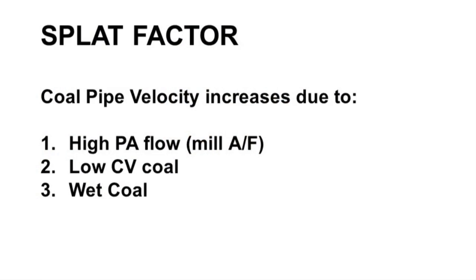I also wanted to suggest that I have seen wet coal cause wall slag problems in the past, and I had a tough time explaining why water or how wet the coal was an influence on the slagging behavior. But I now know that wet coal has the same impact on the pulverizers as low calorific value coal. In other words, wet coal takes a higher coal flow rate and potentially more primary airflow to try to dry the wetness. And so wet coal actually influences the pulverizer performance and could potentially influence the splat factor and resulting wall slags.